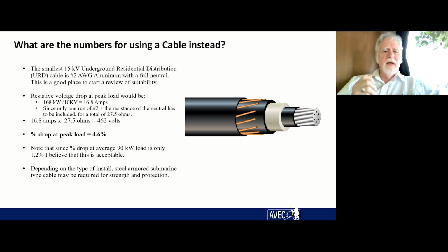You've got to remember that that's at 10 kV. If we run the voltage higher, we can reduce this. And since we normally have 90 kW load, which would only incur a loss of 1.2%, this is acceptable. Yes, the voltage varies, but that doesn't matter so much with MVDC, which I'll get to in a second. Note that the picture I've shown here is not submarine cable. Submarine cable would have a layer of steel on the outside. It would be much more rugged, and you could drive over it all day with snowmobiles, for instance, and not damage the cable.